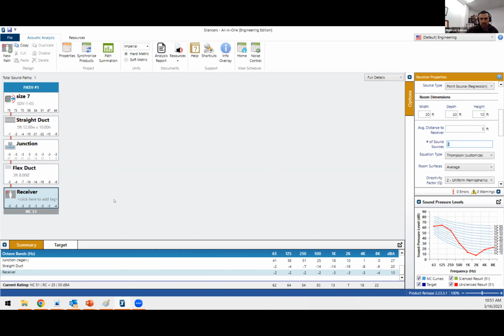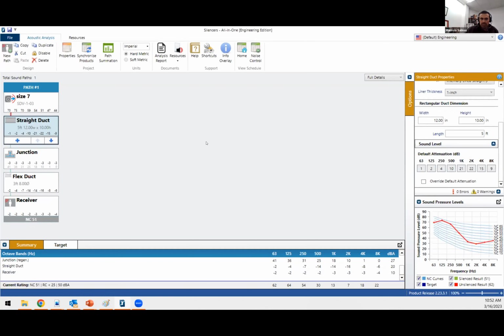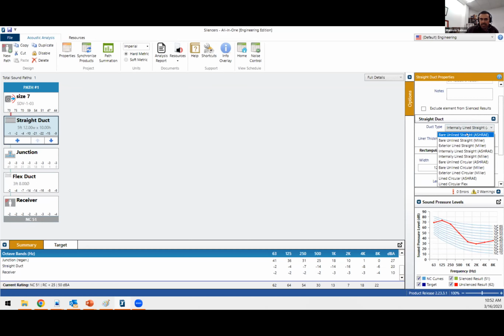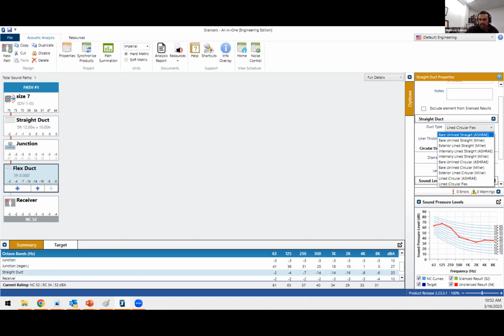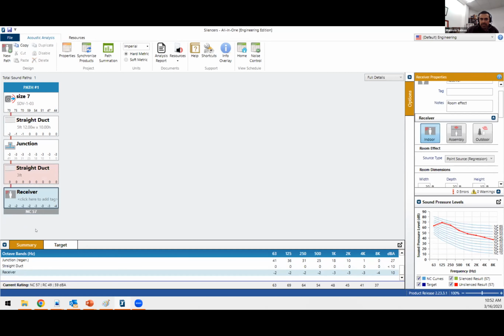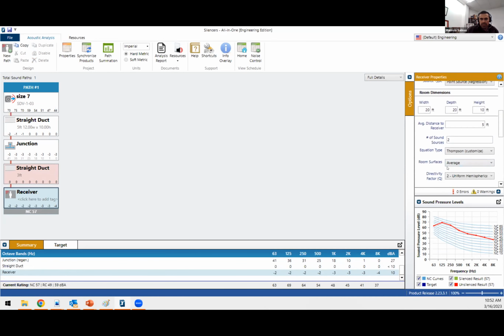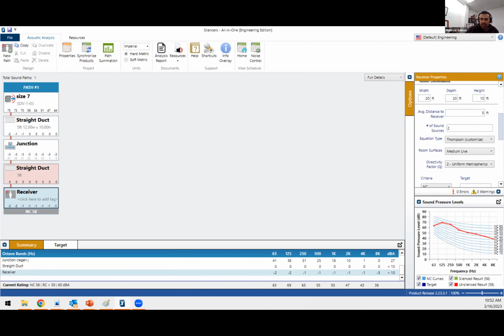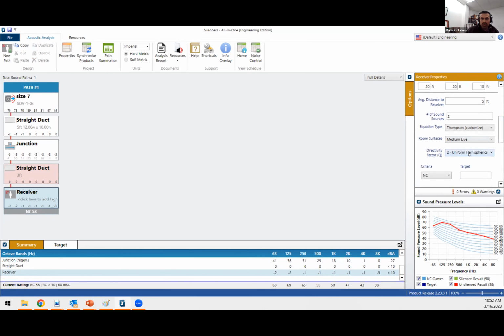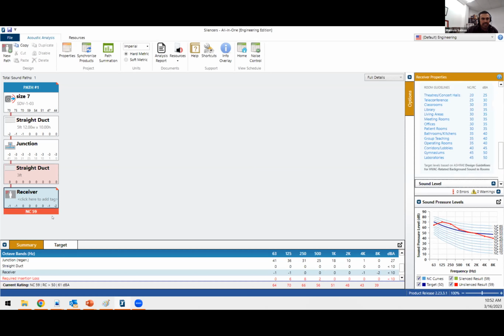If you really want to see how loud the space is going to be, you have to look at the right application. If this is going into a pre-operating room, well, it probably doesn't have lined duct, right? So all of a sudden, you don't have that. And you probably don't have any flex duct either. So then you're starting to get a little bit louder. Then the space is a pre-operating room, so it's not average anymore. It's medium live, right? And you're going to have people standing by it. And if the diffuser is really close to a wall on the ceiling, then you have 2 reflective surfaces. So all of a sudden you have your NC 50 rating for AHRI 880, but in reality it's NC 59. Does that make sense?